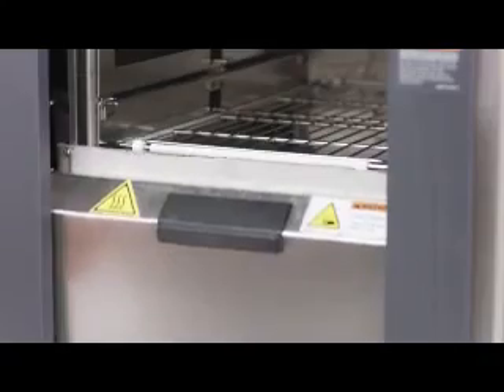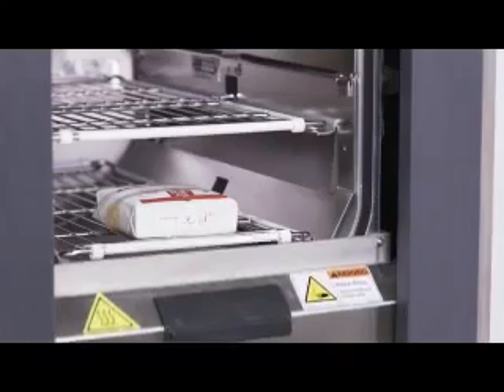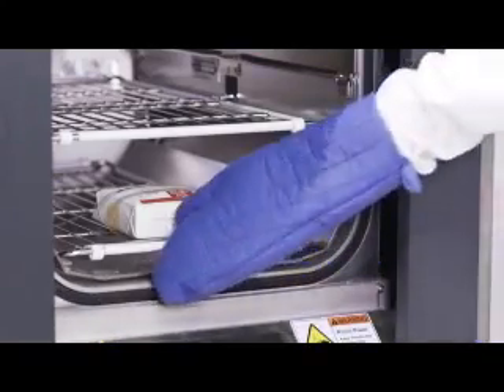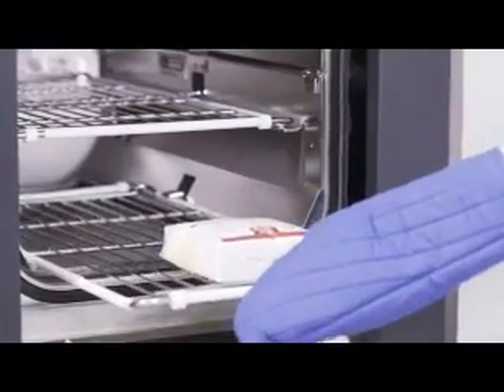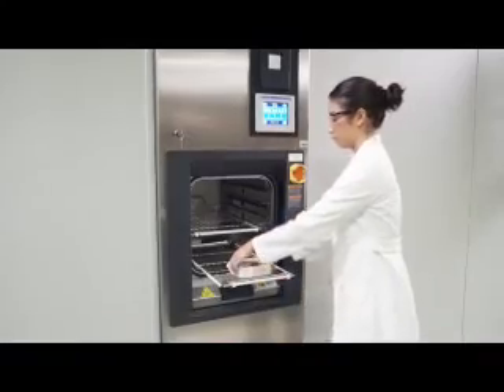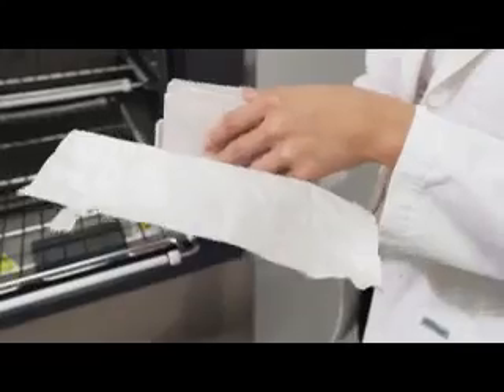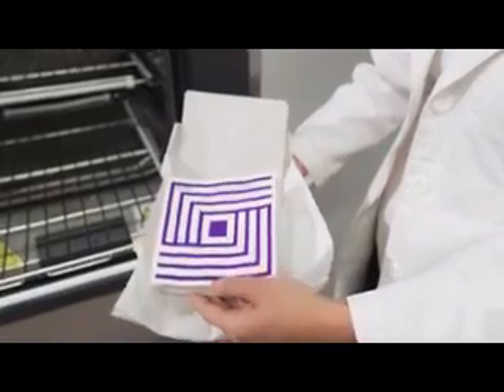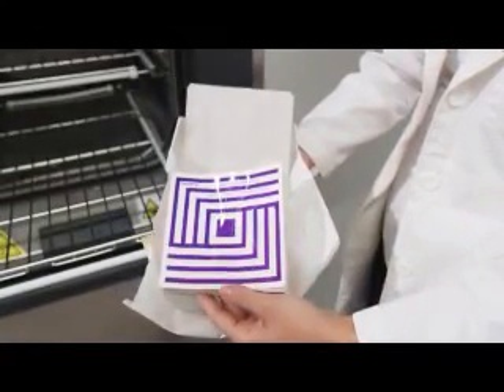This takes 3.5 minutes to complete, and afterwards the chamber can be opened and the test pack inspected. Carefully remove and open the DART test or Bowie Dick test pack. Examine the test sheet indicator for complete and uniform color change. The entire cycle is also documented on the test cycle printout.